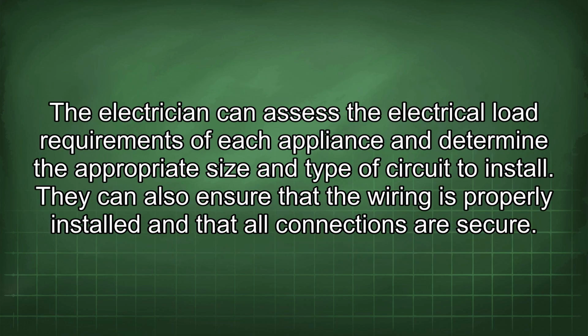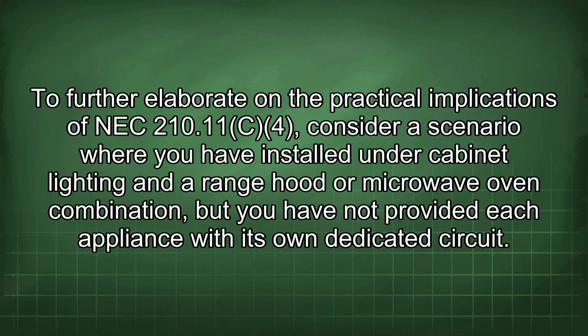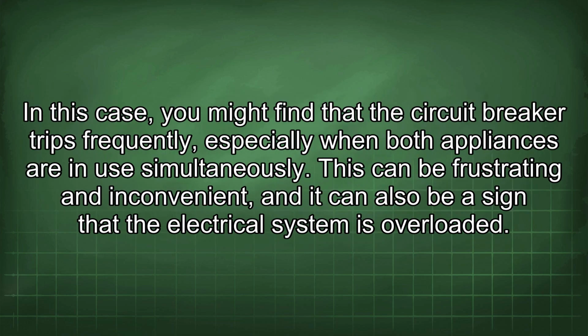The electrician can assess the electrical load requirements of each appliance and determine the appropriate size and type of circuit to install. They can also ensure that the wiring is properly installed and that all connections are secure. To further elaborate on the practical implications of NEC 210.11(C)(4), consider a scenario where you have installed under cabinet lighting and a range hood or microwave oven combination, but you have not provided each appliance with its own dedicated circuit. In this case, you might find that the circuit breaker trips frequently, especially when both appliances are in use simultaneously. This can be frustrating and inconvenient, and it can also be a sign that the electrical system is overloaded.